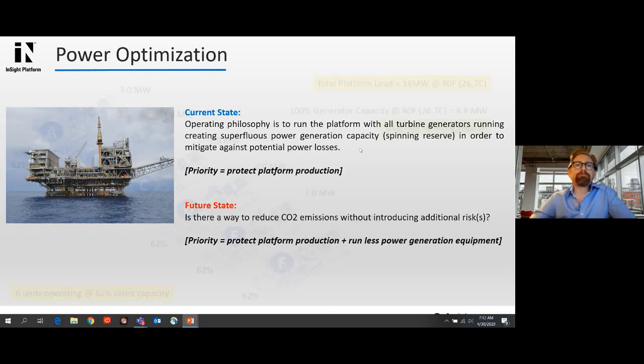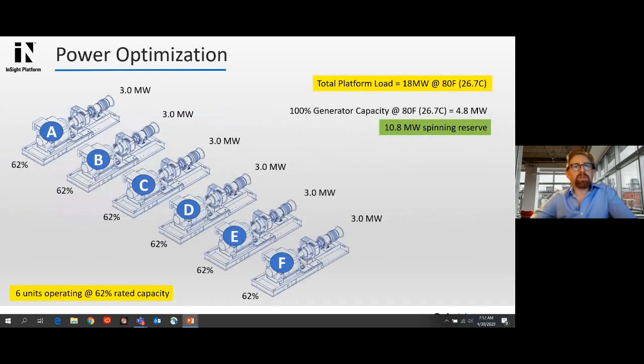equipment. If we look at this example again, we have 6 units in operation, and I looked at the historical platform load, which was around 16 megawatts. So for the purpose of this exercise, I went even more conservative and basically base loaded at 18 megawatts at 80 degrees Fahrenheit or 26 degrees Celsius. So in this application, all 6 units are running at about 62% of their rated capacity. So they're basically each generating 3 megawatts of power. So what this means is that since all of these units are capable of 4.8, each unit's capable of going 1.8 megawatts higher, we have a 10.8 megawatt spinning reserve available in this application.